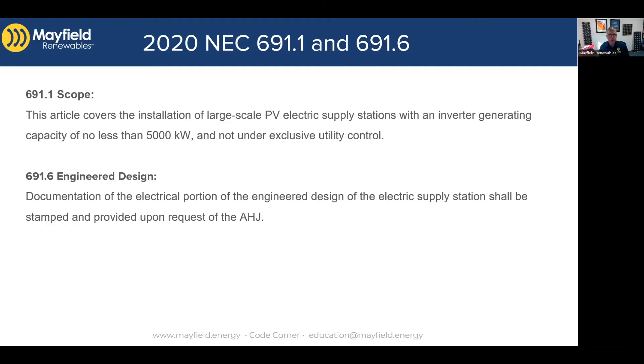Let's talk about the scope. Article 691, like every other article within NEC, has a scope. You see that language here on the screen. It says that this article covers installation of large scale PV systems with an inverter generating capacity of over 5000 kilowatts, and not under the exclusive control of the utility. The 5000 kilowatts is the same as five megawatts — not a huge system really anymore these days, but it is a large system.